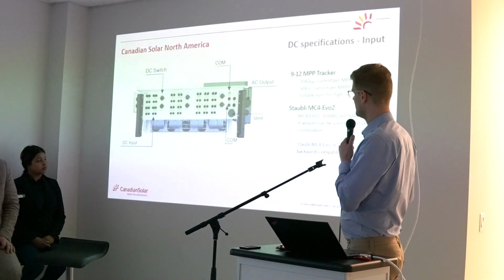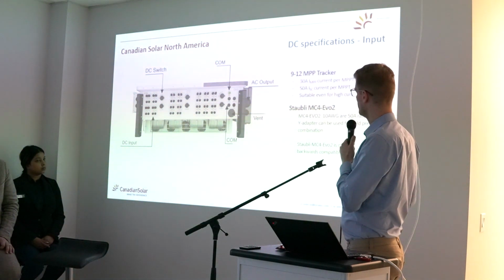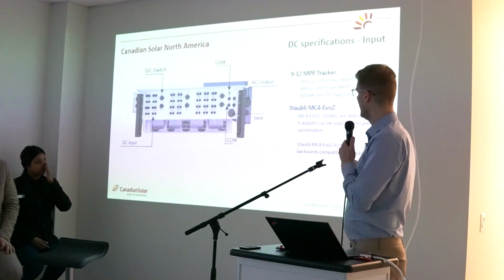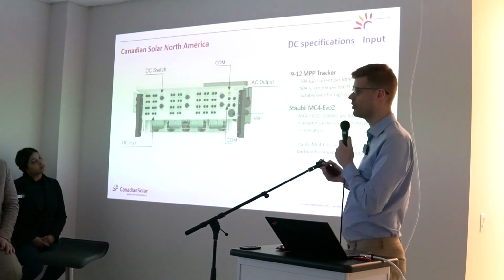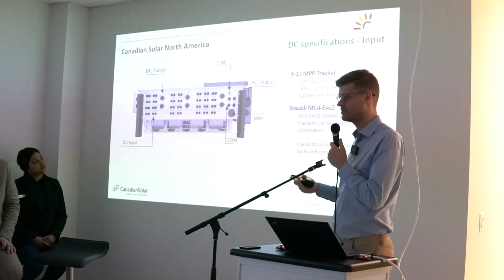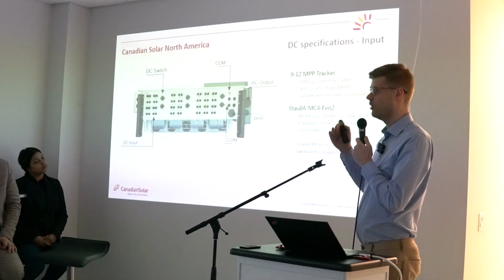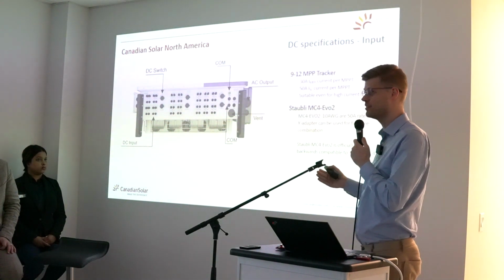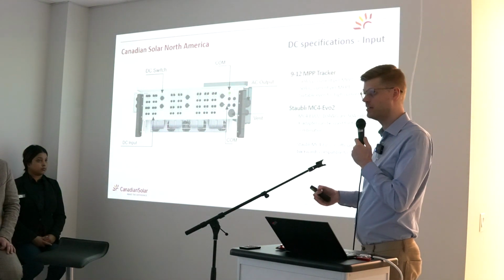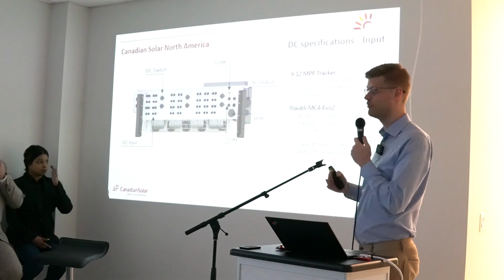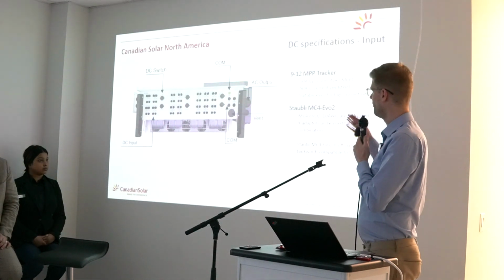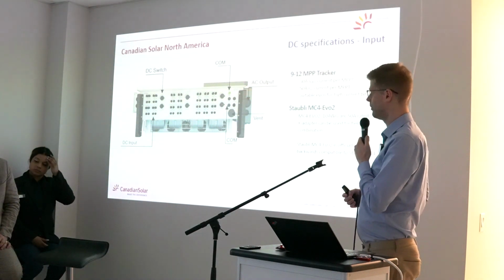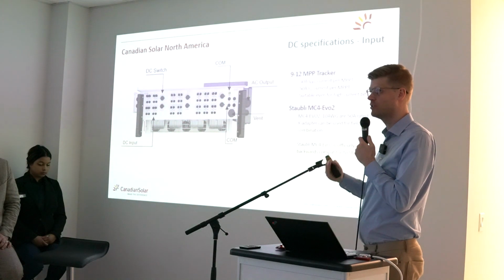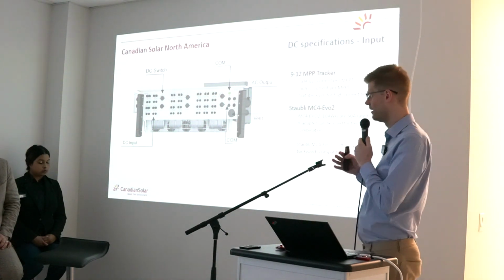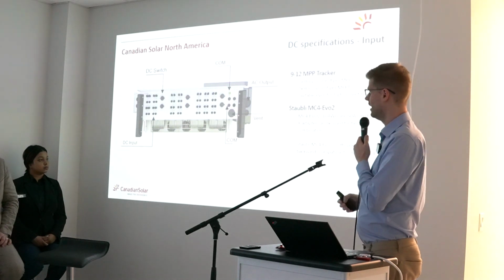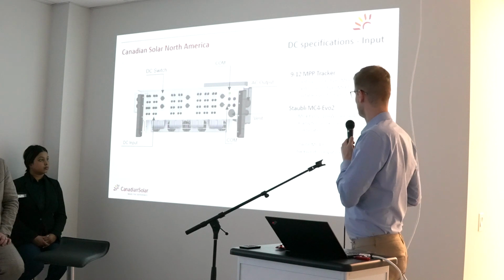One really big advantage of the CSI inverter is that the inputs are designed to accommodate a very high short circuit current. And the very high short circuit current capability of the input is important for nowadays high current solar modules, specifically for modules that are also bifacial, because once we have the high ISC current, a lot of designs use a certain multiplier and a certain extra percentage on top of the ISC value for the backside production of the system. So with a 50 amp ISC current capability of each input, you're pretty much open to any current and probably for the next 2-3 years a panel size that is on the market that you're really open to monofacial as well as bifacial.